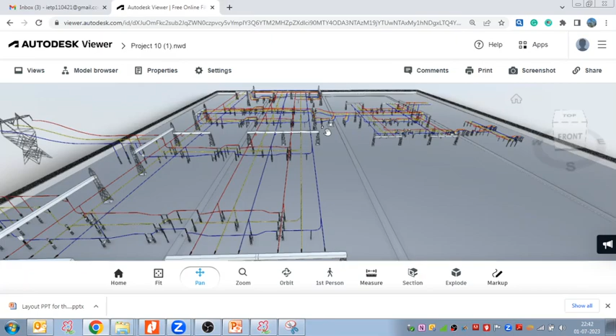So this is the two main bus bar exit. As I told, if we have the double main and transfer bus bar scheme, the double main bus will come together, but the exit bus bar location, orientation and position will be towards the line bay, not towards the transformer bay, not towards the transformer. Priority exit is the line. This is what I'm trying to explain.